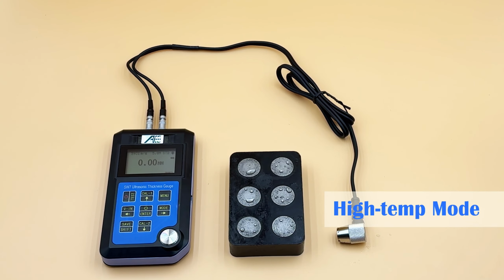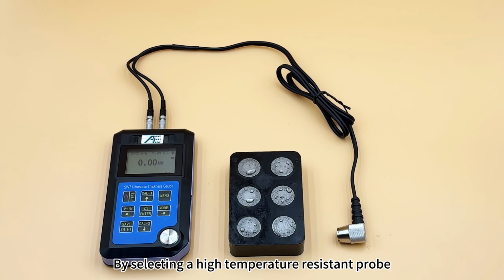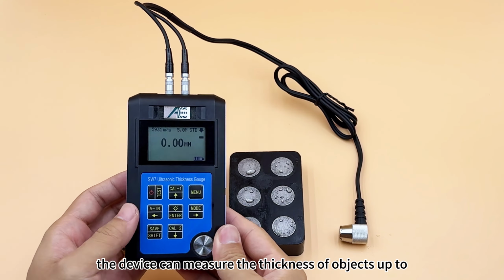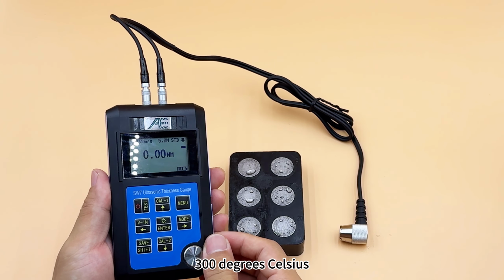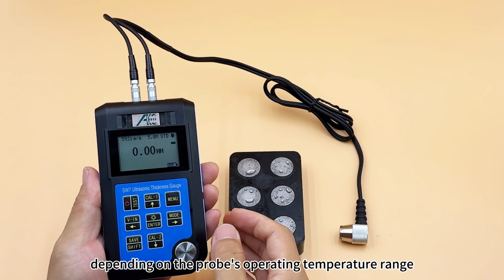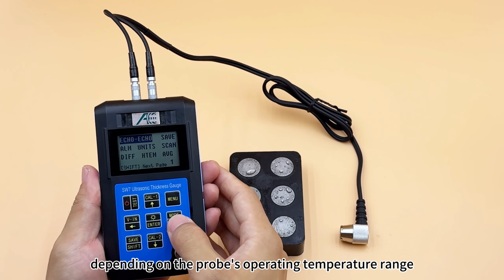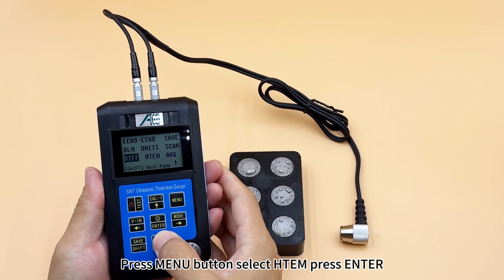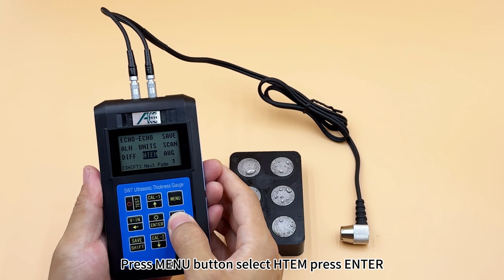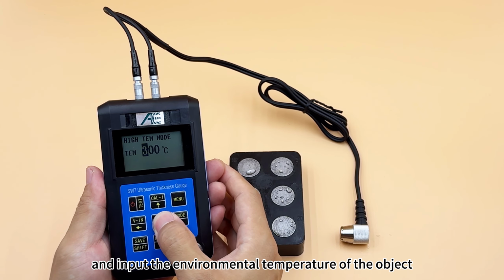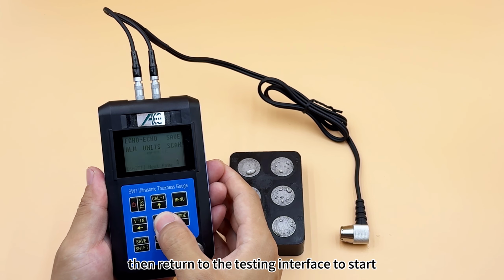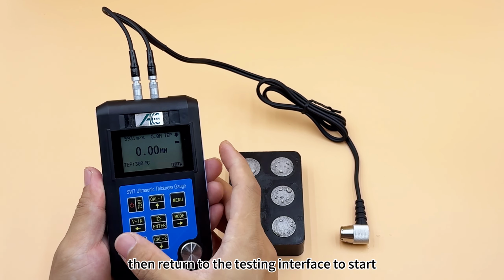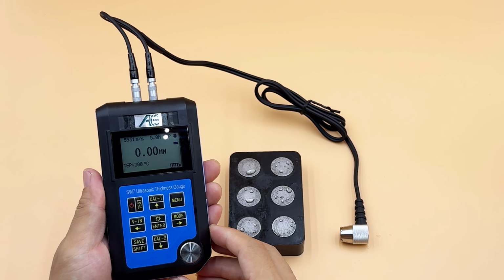High temperature mode. By selecting a high temperature resistant probe, the device can measure the thickness of objects up to 300 degrees Celsius, depending on the probe's operating temperature range. Press Menu button, select HTEM, press Enter, and input the environmental temperature of the object. Then return to the testing interface to start thickness measurement.